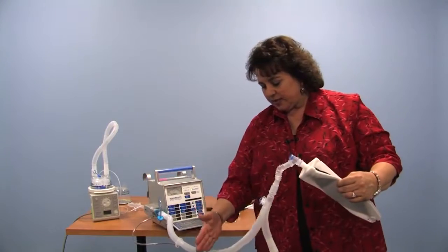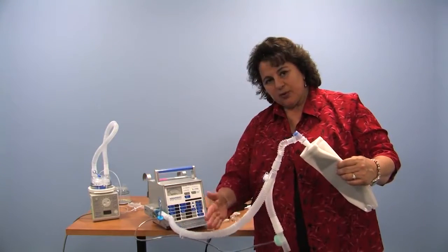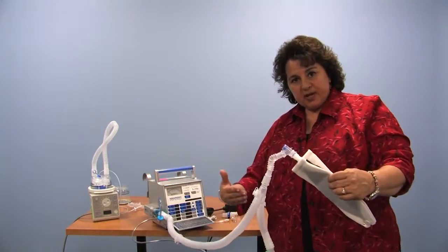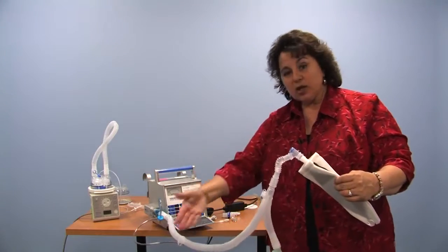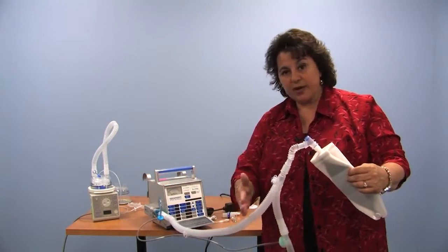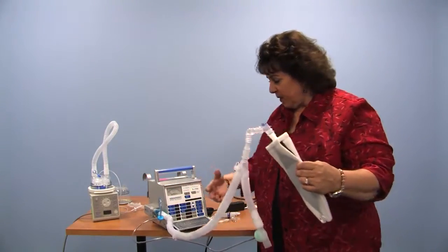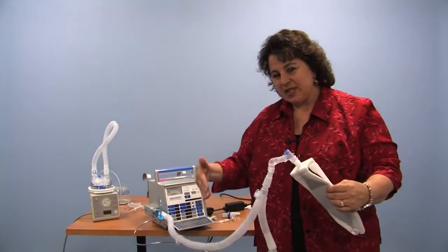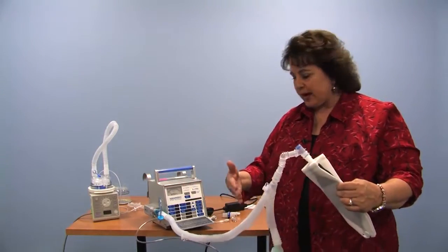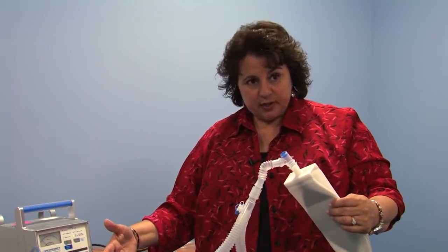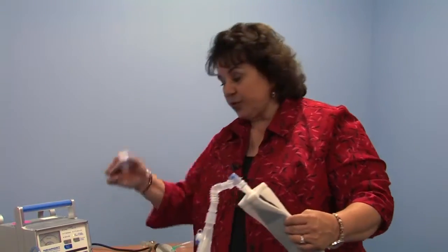You can see there are areas here where you can cut it. So if your patient's in a wheelchair when they go out and you don't want long tubing draped, you can cut it short and make it appropriate length for them. I cut it short just for the purpose of today, so we didn't have a lot of tubing draping around. So this would be an adult non-heated wire circuit for travel outside the home, for use in the home if you're going to use the heat moisture exchanger.